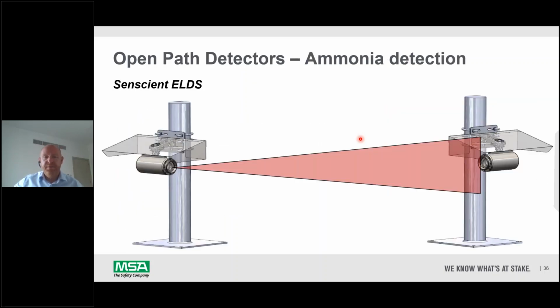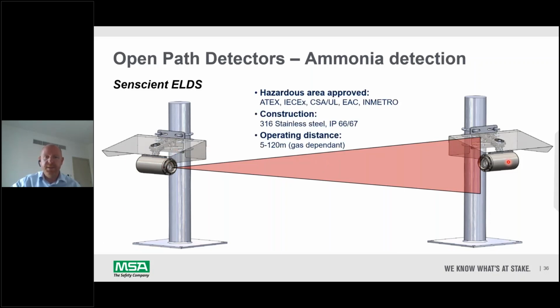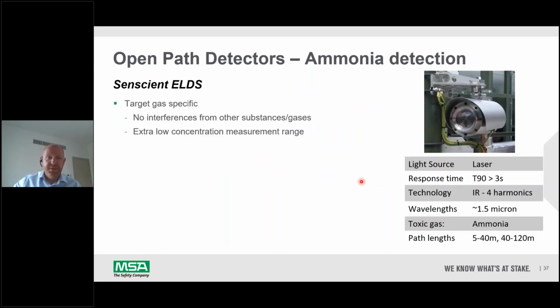So what we have for it is our open path gas detection system. It's a gas detection system which has an infrared or laser beam. You have a source and a receiver up to about 120 meters apart. And these will only alarm when one particular kind of gas is present, because false alarms are a huge issue for large facilities. They're very expensive, and they're dangerous as well. So if a gas cloud or a small part of the gas was to go between these beams, an alarm would happen, and the alarm happens very, very quickly. It's less than 3 seconds to detect the ammonia leak from these systems.